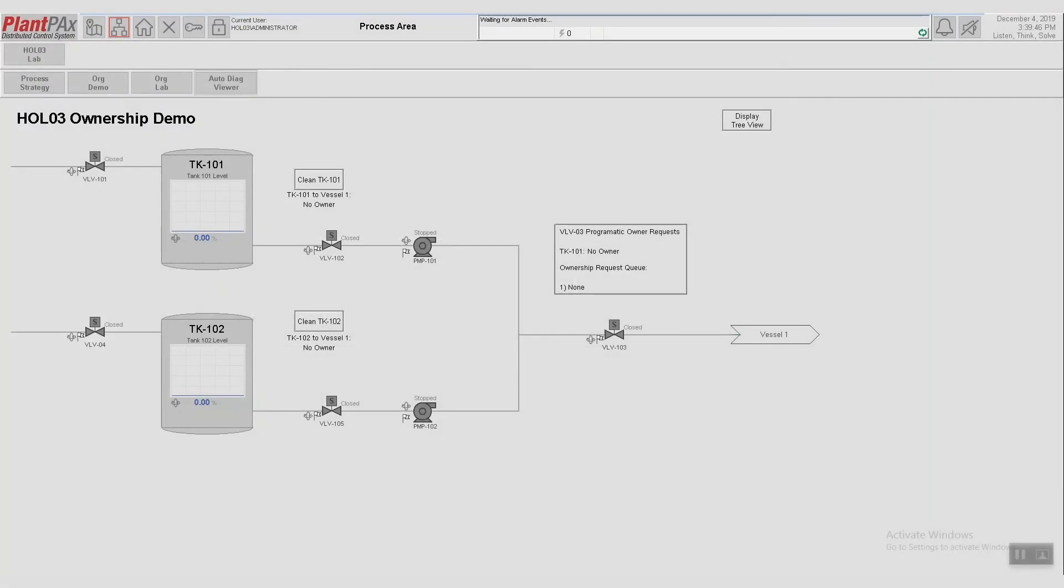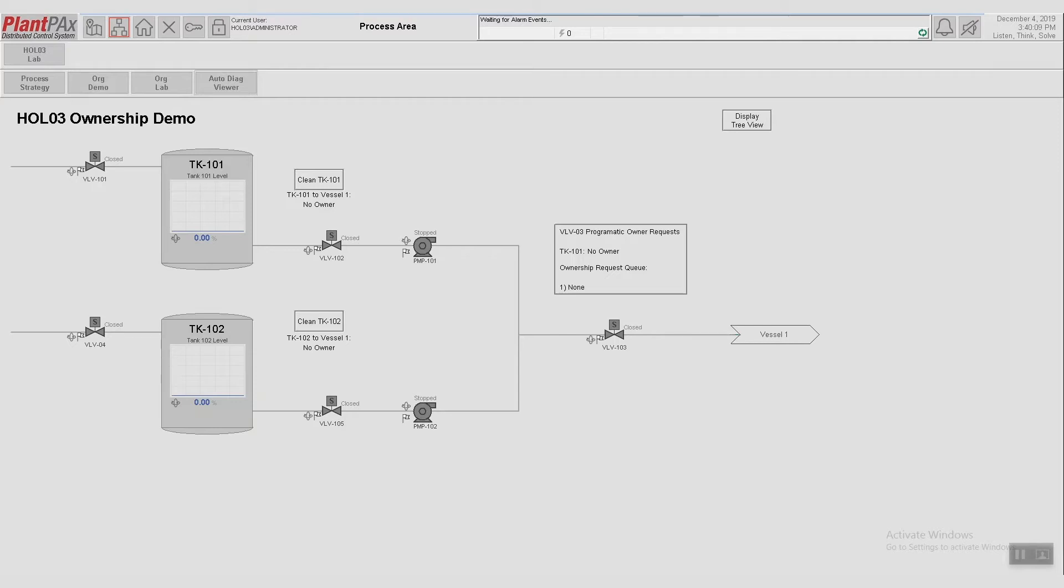Here I have an equipment overview HMI screen with a number of devices that make up two tanks. As you're operating your sequences in your plant, you're typically operating multiple devices at a time. In 5.0, our ownership and arbitration native functionality allows you to build up equipment groups without writing any custom code. From these equipment groups, you can send commands down to all of the devices or propagate statuses upward.